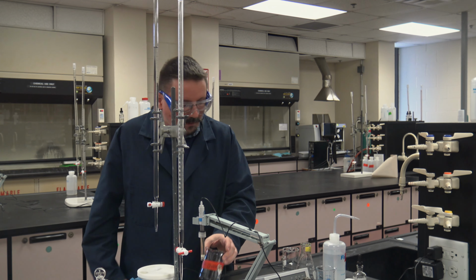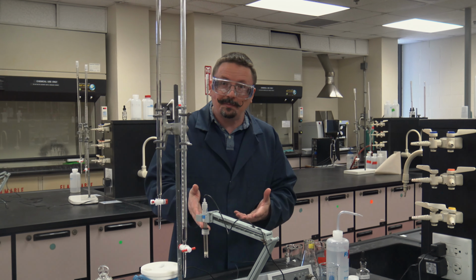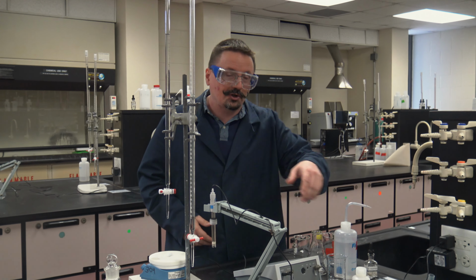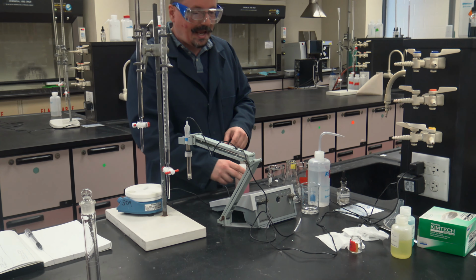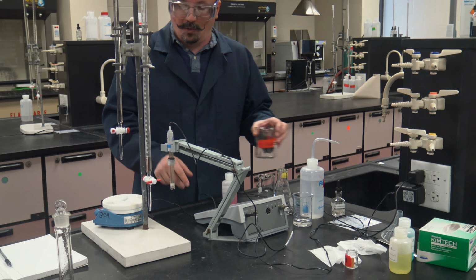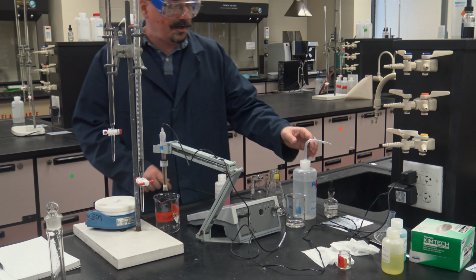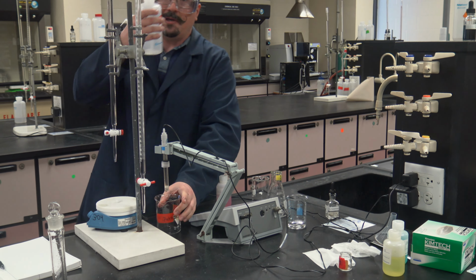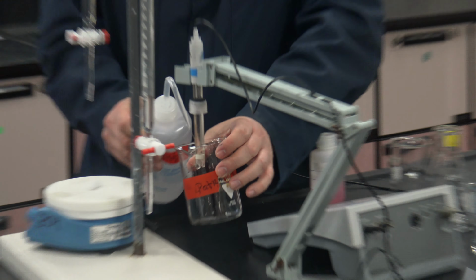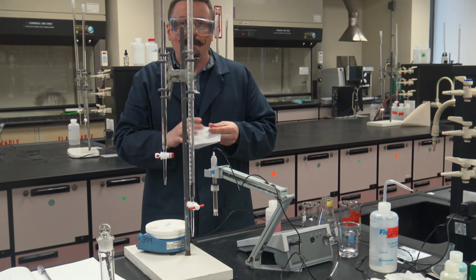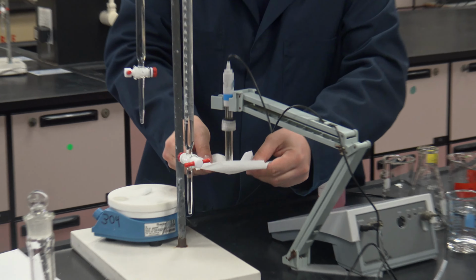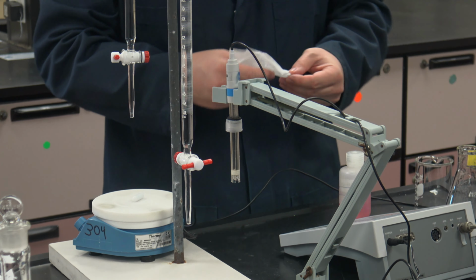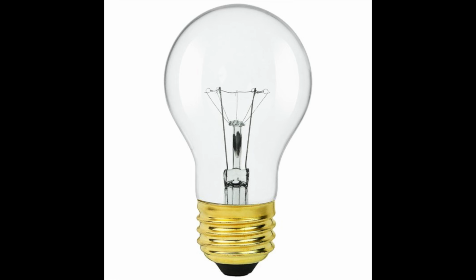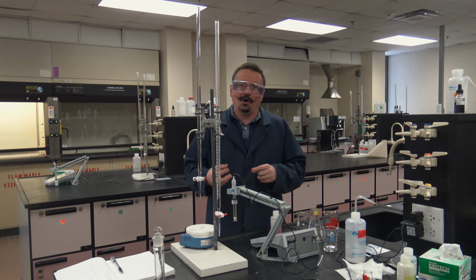So the first thing you're probably going to want to do, if you're the first person on the pH meter or the pH probe, is calibrate it. It only needs to be calibrated once per day, but if no one's done that yet, if, like I said, you're the first one on here, you'll have to do that. Get a waste beaker, get some DI water, just give that pH probe a little rinse, and then I'm going to come in and just dab away that excess water. I don't ever want to rub or wipe or use a lot of pressure, because there's a glass bulb on the bottom of that pH probe. That's the interface that's going to interact with our ions and record that value.